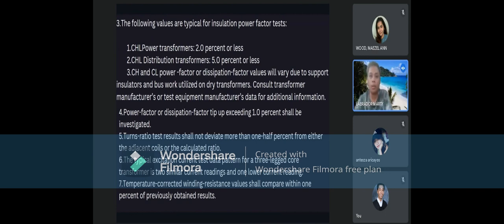4. Power factor or dissipation factor tip-up exceeding 1.0% shall be investigated. And 5th, turns ratio test results shall not deviate by more than 0.5% from either the adjacent coils or the calculated ratio. 6. The typical excitation current test data pattern for a 3-leg core transformer is 2 similar current readings and 1 lower current reading. 7th is temperature corrected winding resistance. Value shall compare within 1% of previously obtained result. Next one.